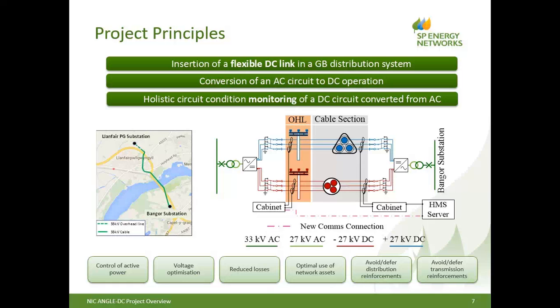We're going to actually put some isolated earth switches and disconnectors on the outgoing circuits to give us ease of earthing up and isolation for changing pin insulators or faults on the actual circuits themselves. And then it goes in a mirror image back at the other end substation. You'll also see a couple of other things on there. Near the overhead line, you'll see some loops. Towards the right-hand side of the cable section, you'll see some loops which go into a cabinet.